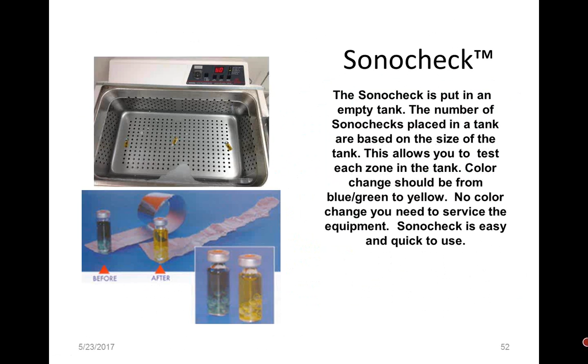So how do I verify the sonic cleaning? If you want to check cleaning right now through the literature, when I put this together, there's the Wash Check U and the TOSI. Those are meant for checking the cleaning. Is it cleaning? Not if there's sonication, but for cleaning and reading the IFUs. So you want to make sure, no matter what you use, does the soil represent what you're trying to clean? Are you trying to clean blood off a surgical instrument or something else? The design, is there a challenge to it? Does it represent the most challenging design of, say, your box locks? Is it supported by peer-reviewed and non-peer-reviewed literature? And that's very important in this day of evidence-based practice. What is there to support that this is actually doing what it's supposed to do? And does the soil represent and correlate to the cleaning kinetics of blood?